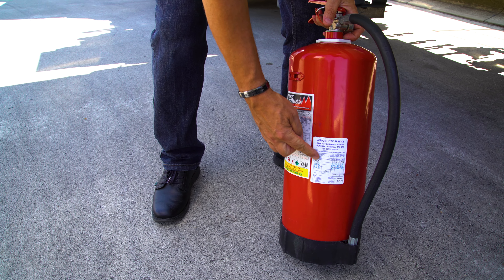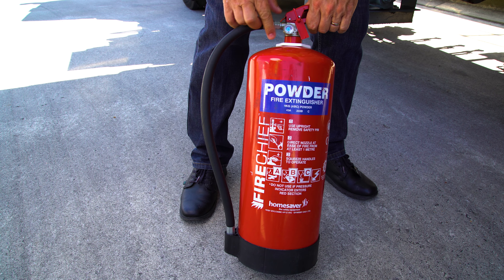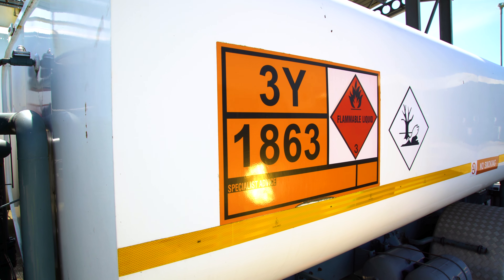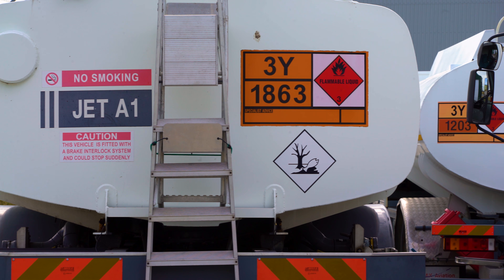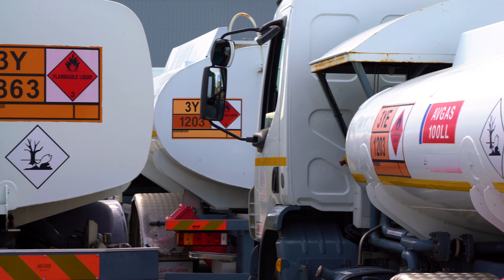Checking the gauges and the overall condition of the fire extinguishers is important, and the correct checks should be noted on the side of each extinguisher. There should also be correct product signage on the tanks themselves, from warning labels to no-smoking signs and no-hazardous-product-to-the-environment notices.